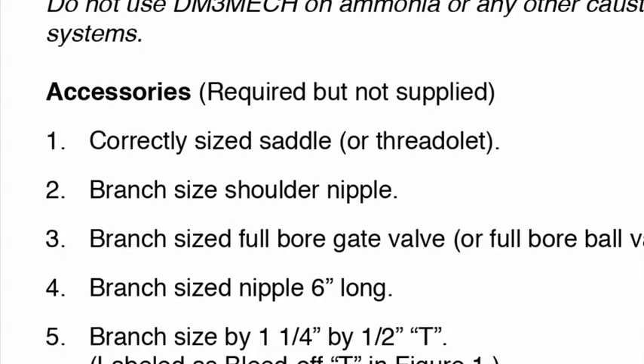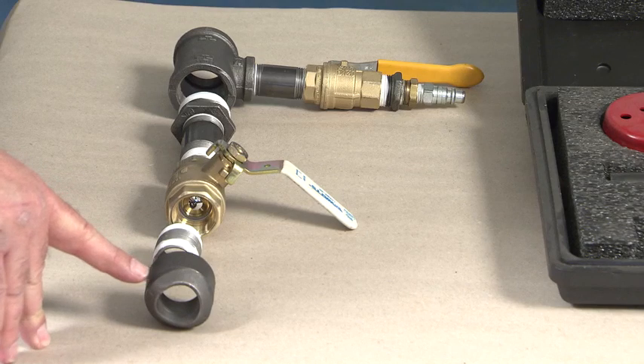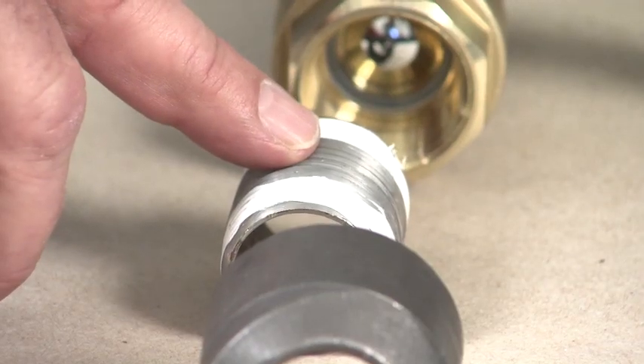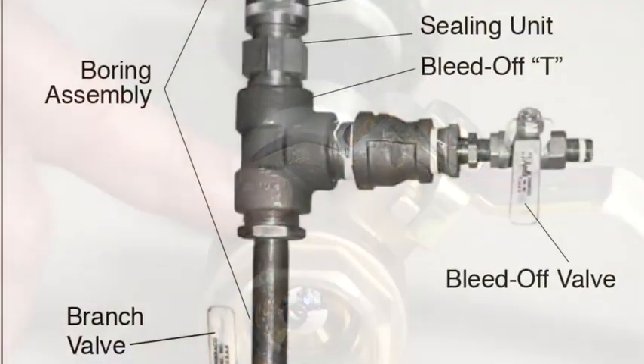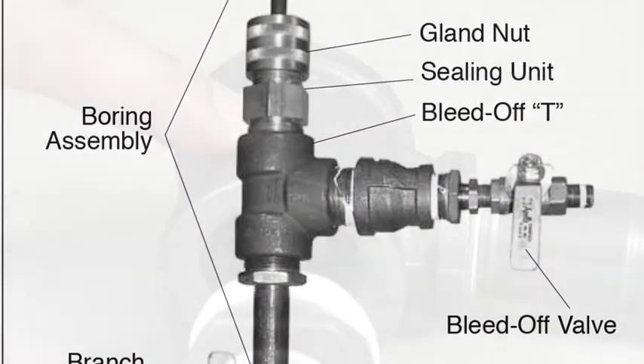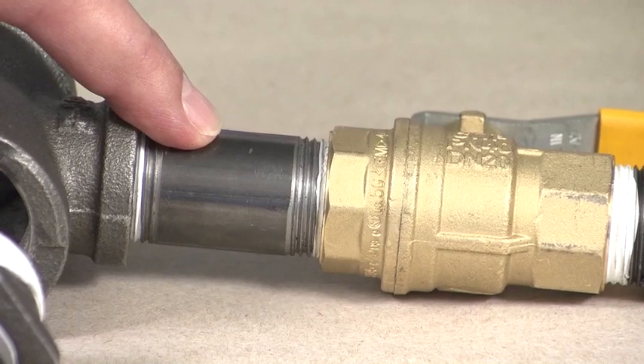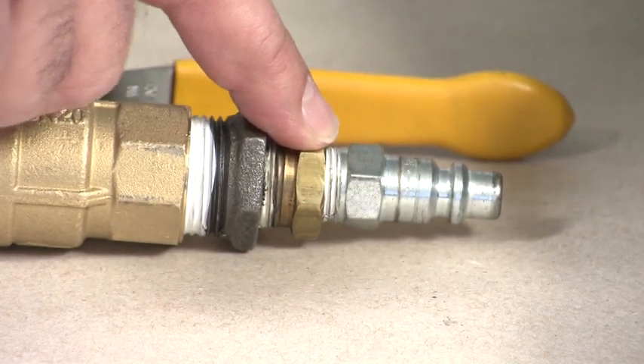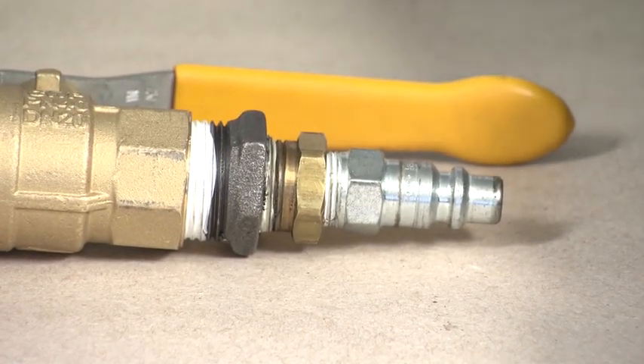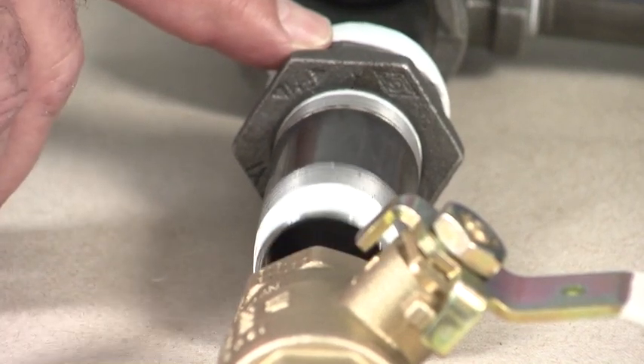These accessories are required but not supplied for use with the DM3 Mech. A main branch assembly that will be permanently fixed to the mainline, which includes a correctly sized saddle or threadolet, a branch sized shoulder nipple, and a branch sized full bore gate or ball valve. A boring assembly is also required, which includes a 1¼ inch pipe T or inline T reducer, a pipe nipple to match the T, a valve or hose bib, a hose connection for pressure testing or for flushing chips, and a branch sized nipple 6 inches long and reducers if needed.